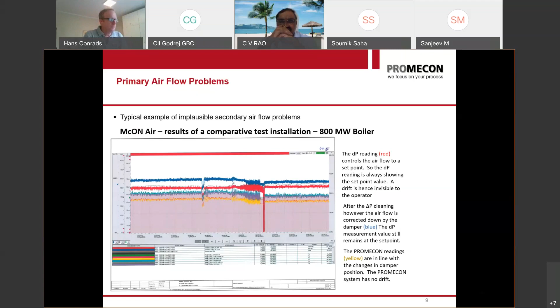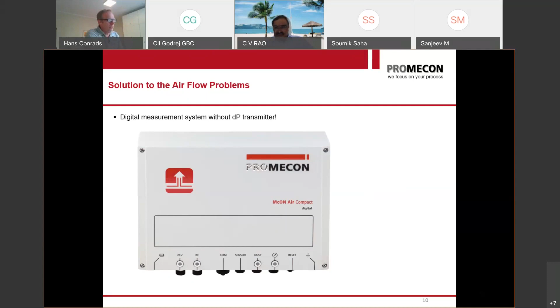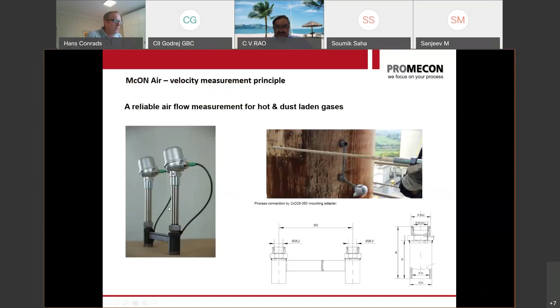How do we solve this? Promecon, first of all, has introduced an airflow measurement, which is now part of most German new coal-fired power stations. It is a digital system that measures the airflow not by delta P, but in a digital way, which is drift-free. No drift, always accurate. How do we do that? We have two sensors aligned, and these two sensors measure the electrification of the airflow. Let me show you this.